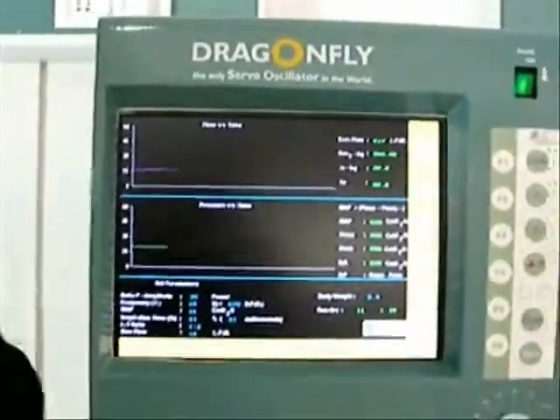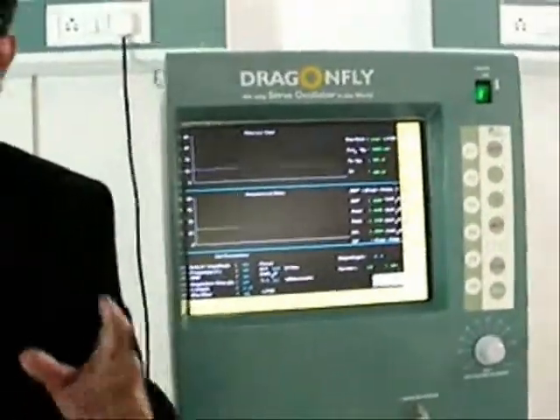When I say it's the only servo controlled oscillator in the world, it implies certain things. For example, if you have seen a contemporary Sensormedics 3100A oscillator, you would have noticed that if you set the pressure and then alter the flow, the pressure either falls or goes up. So the pressure and flow go hand in hand. If you increase the flow, the pressure also increases. If you reduce the flow, the pressure also reduces. So it's interdependent. Same thing is here.